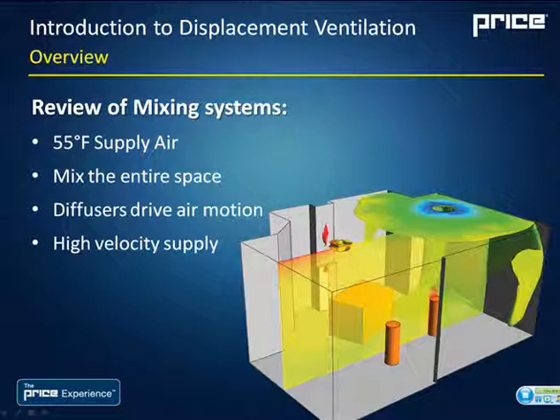Now, to review the two systems, starting off with our standard mixing system, we have 55-degree supply, typically through a ceiling diffuser, where we would have a high-velocity diffuser. And what it's going to do is it's going to mix the space. So what you're seeing in this picture is a CFD printout of a simulation done with a ceiling plaque diffuser. And basically you're seeing the temperature distribution across the room pretty well even. The only zones that are not around 74, 75 or room temperature is the area right at the exit of the slot and right at the return. Otherwise, the rest of the room is pretty well even temperature.